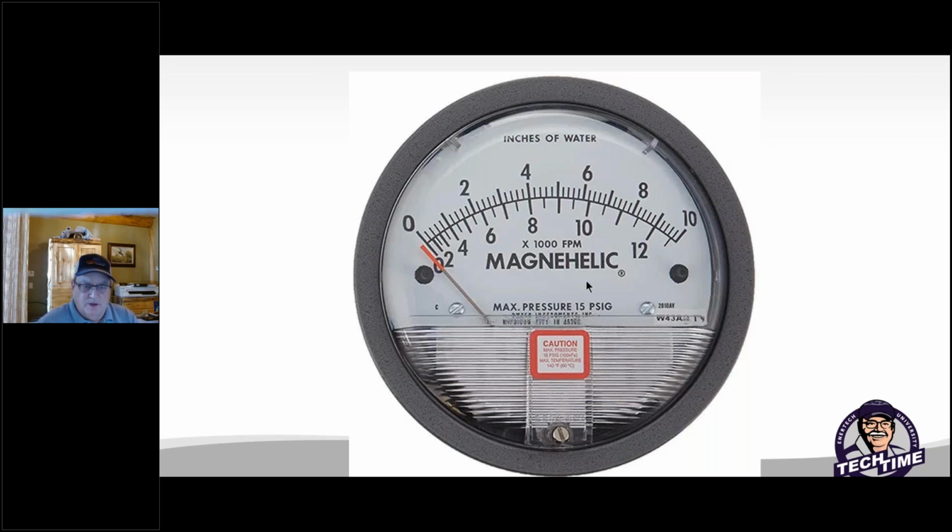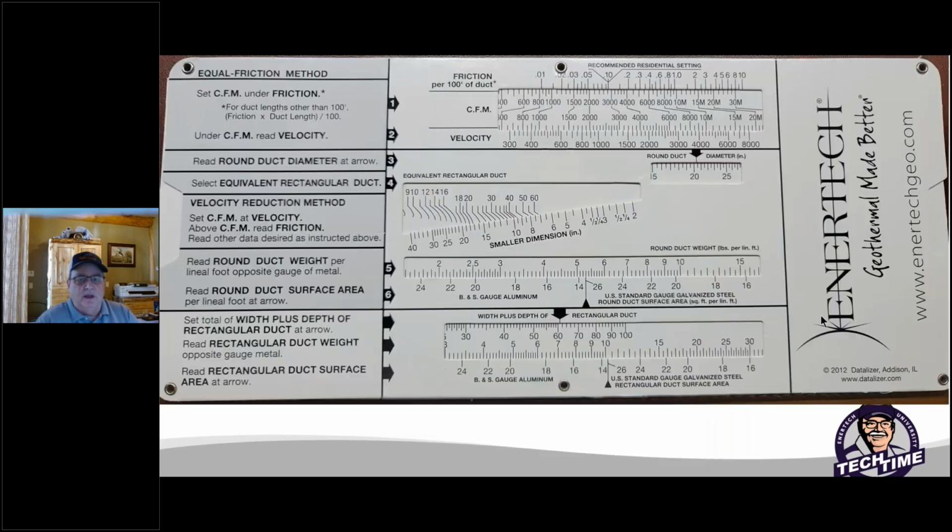But again, make sure you get the kit with the pitot tubes, and they have the hose kit with them, so you can measure real accurately. What's the importance of a ductilator? Well, as you know, sizing and designing the ductwork for airflow, CFM is really critical.